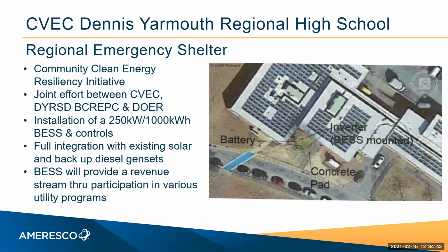Yeah, it does. The approach might change a little bit if you had energy storage, in that you could keep the generator running at a higher efficiency. But generally speaking, since the solar is with respect to carbon 100% efficient, it still makes sense to reduce the output of the generator down to the minimum that was programmed in for this project. Excellent.